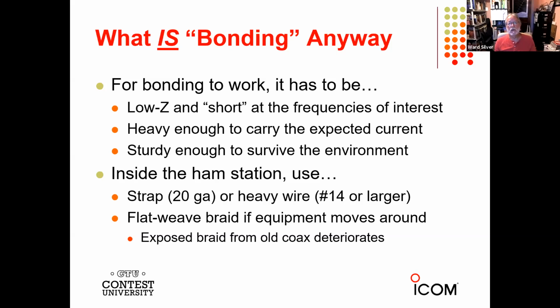Inside your station, you can use a lot lighter stuff. The standard used by everybody that builds installations, and that's commercial and military, is solid strap, 20 gauge copper strap. You can get flashing, rolls of flashing, and cut it up. The standard is about 1.5 inches or 2 inches. If you've got a relative in the roofing business, you can often get scrap flashing from them, or you can use heavy wire.